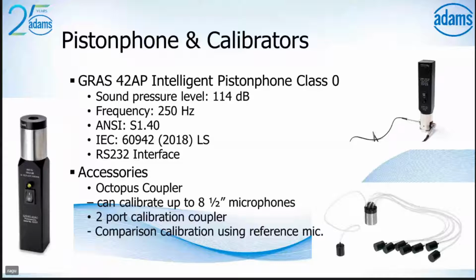For a good acoustic measurement, it is always recommended that you start your measurement by doing a level check and a functional check of the microphone which you're using. So this helps you to save a lot of time. Instead of going one by one, you can do the functionality test and calibrate up to 8 microphones at the same point of time.